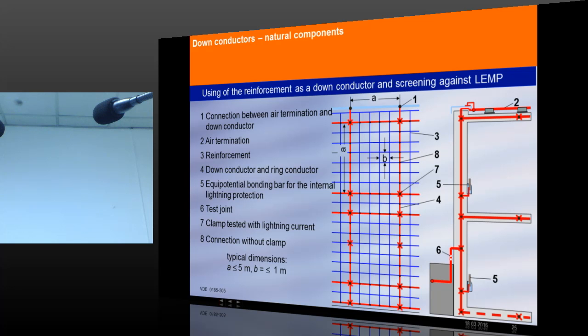Once we talk about this, that means I am explaining to the architect or the civil engineer that the steel in this particular pillar has to come out of the structure. Then they don't agree because of corrosion. Because a small corrosion of this particular conductor will spoil the whole building, because we are designing the building for the next 50, maybe 70, 80 years. So this is not a good engineering practice as per the civil engineering rules, but there are some ways.